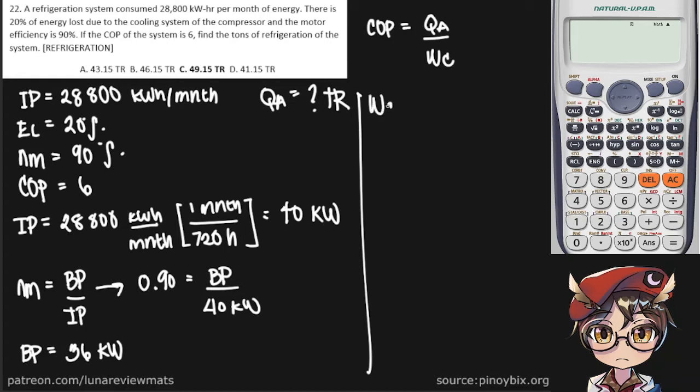First, we should account for the energy loss by multiplying our brake power by 1 minus the energy loss in percent. This is 36 kilowatts times 1 minus 20%. Let's quickly compute for that. We get a compressor work of 28.8 kilowatts.